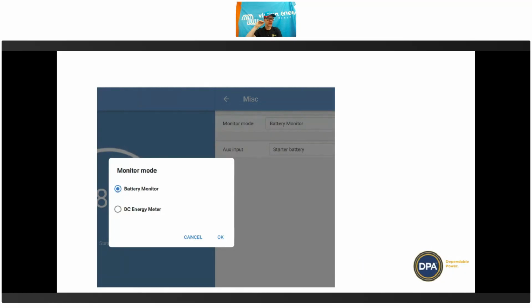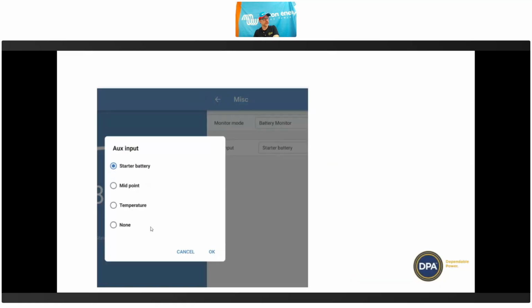You can use this to monitor just say one particular DC load. And when you change it to DC energy meter in here, you can then also choose from a bunch of types of energy meter like pump and a few other things. And then it will come up as that. Instead of coming up as a battery monitor on the Cerbo, it will come up as a DC energy meter, and it will show nicely on all the graphs and things like that. That can be quite useful for some things because you can then turn things on and off according to those values. And then if you were to use those other functions I was talking about before for that second voltage input, they're just set up here in the miscellaneous section of the settings: starter battery, midpoint, or temperature.